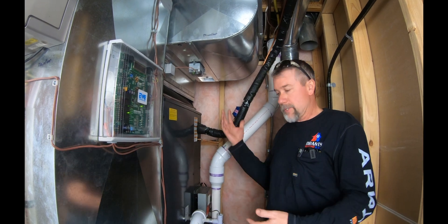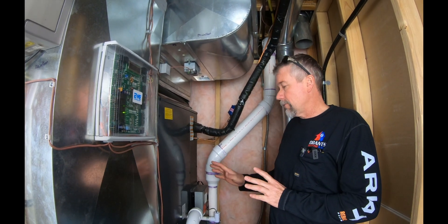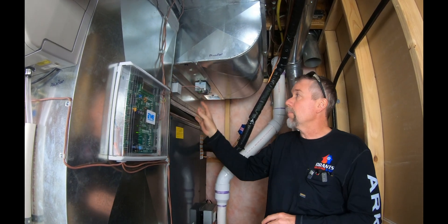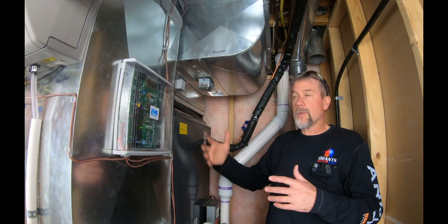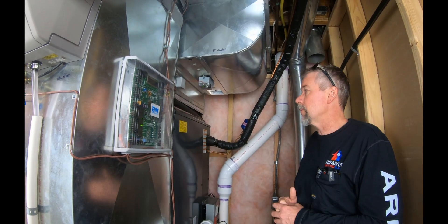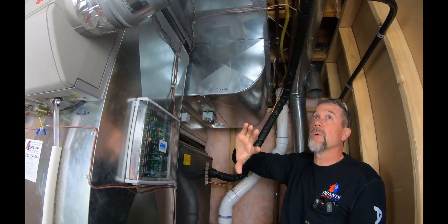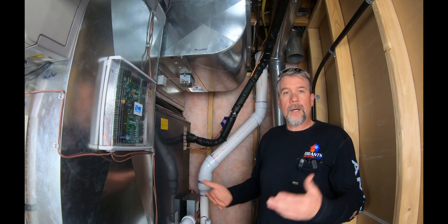Here at Grant's Heating we don't use bypass dampers — that's a whole other subject about bleeding off air and just turning it right back into the furnace. Instead, we added zoning: a zone damper here and one on the back side, brought into our EWC controller. We have a temperature sensor in here which gives us more information on system operation. So we've taken the two furnaces and put one unit in with dampers on each side to control the two levels using two Daikin One thermostats.